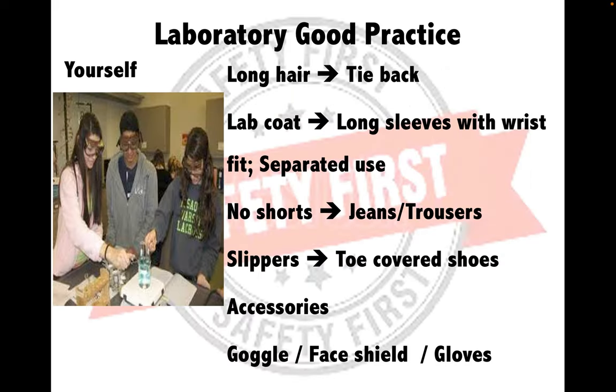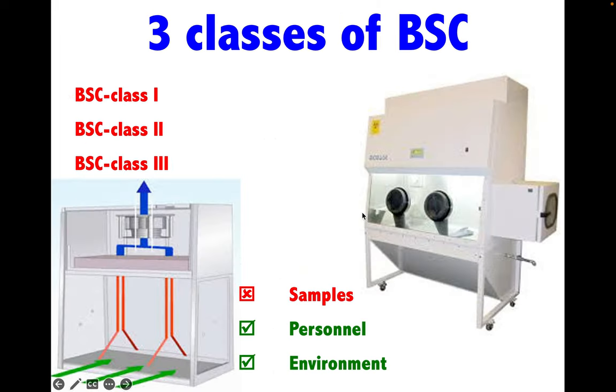BSC class 3 is absolutely unique, designed to compartmentalize from everything using a gas-tight negative pressure enclosure. A HEPA filter must be used for both inflow and exhaust air. It contains attached long-sleeved gloves. We are not permitted to have BSC class 3 as it is associated with the most hazardous pathogens, which are prohibited by Thai law.